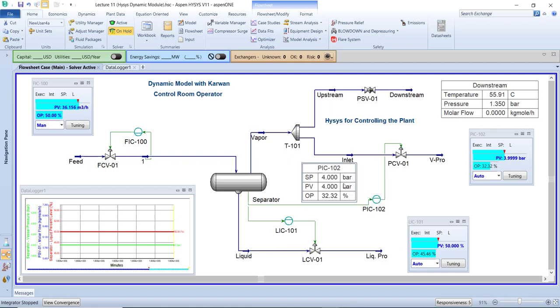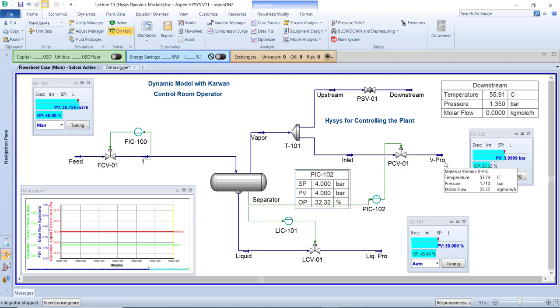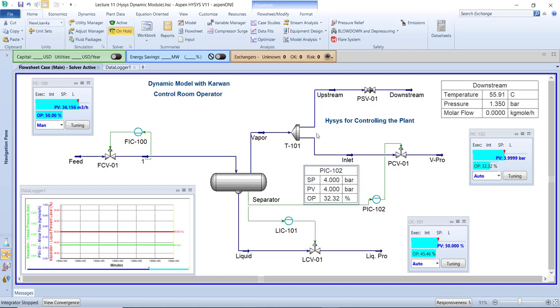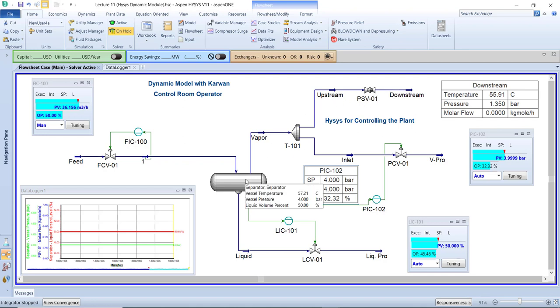To control the pressure, the vapor outlet from the top is split into two lines. The first has a PCV — pressure control valve — that is the main line for the vapor product in normal operation; all the gas goes through this line. The second line has a PSV — pressure safety valve. For any equipment in the plant, we must have another piece of equipment to protect the main equipment, and the PSV serves that purpose.